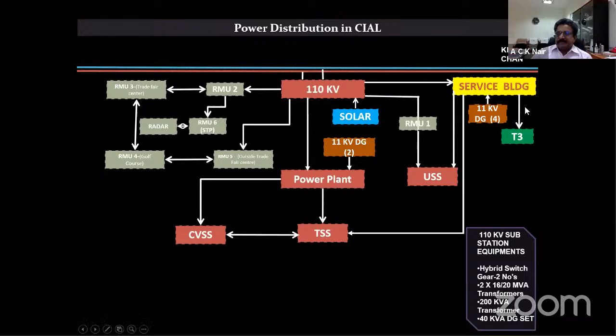One substation serves the cargo area, the second serves the terminal buildings, and another serves utilities such as the air traffic control tower and navigation lights. We also have another substation for T3, and as per international specification, we maintain redundancy in the power distribution system, with all power centers or 11 kV substations connected through ring mains.